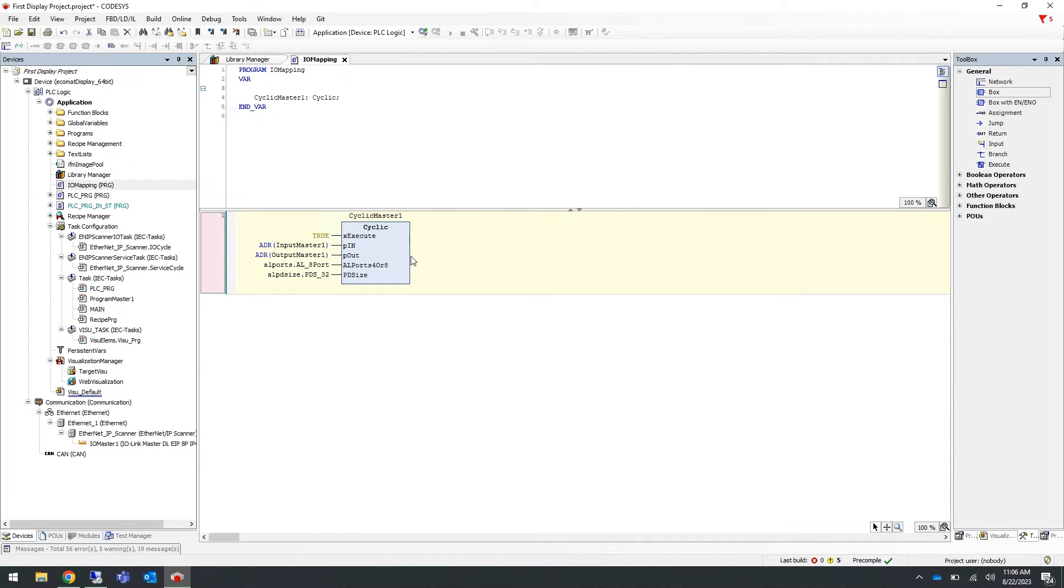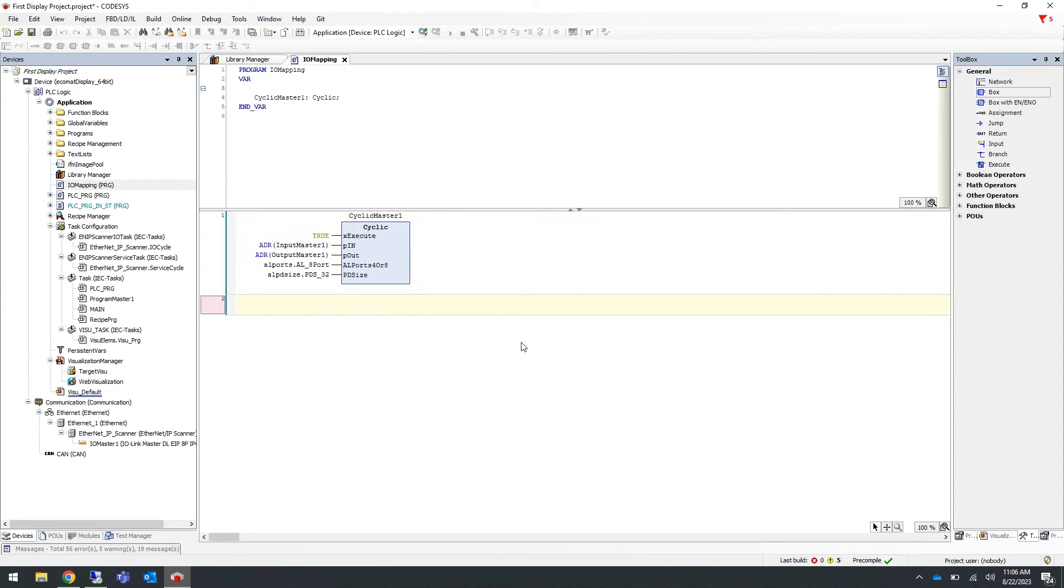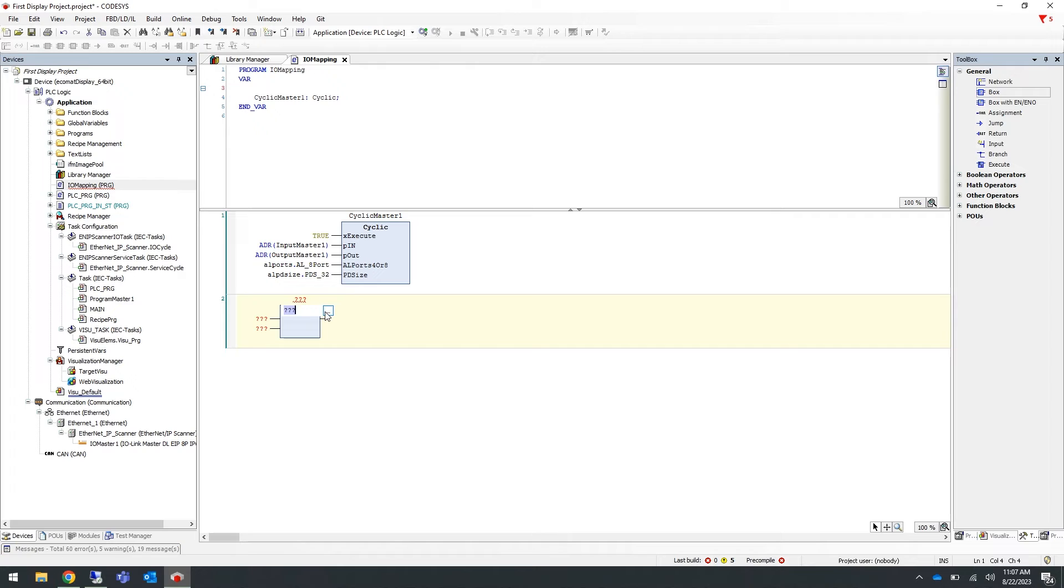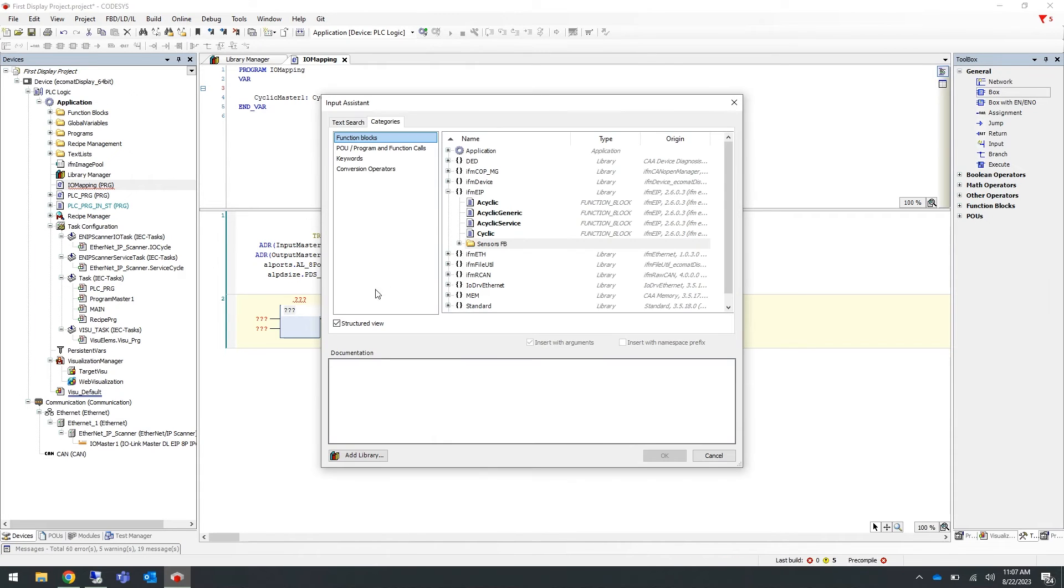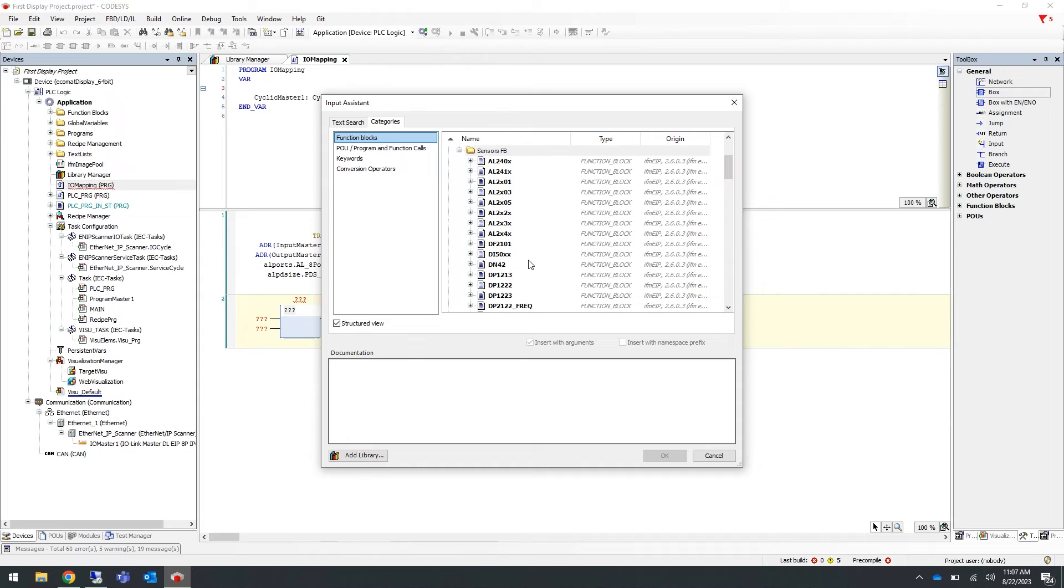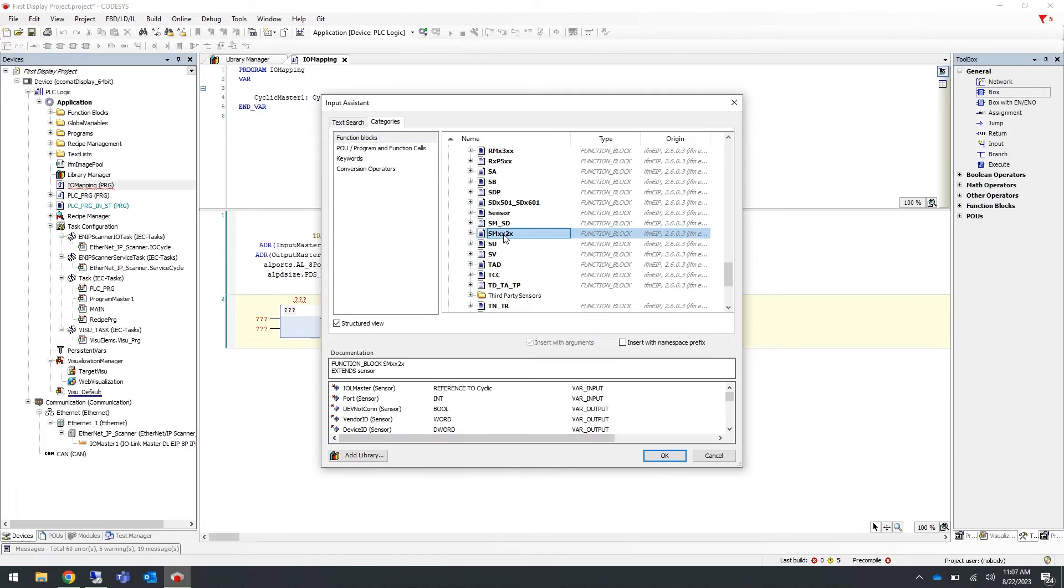Now to add an IO-Link sensor function block, create a new rung and drag in another empty box from the general toolbox on the right-hand side. Go to the three question marks on the inside and the three dots, and navigate to the sensor function block folder inside of the IFM EIP library. In this example we are using an SM6621 flow sensor, so if we scroll down to the S's, we will find the function block titled SMXX2X. Select that and press OK.